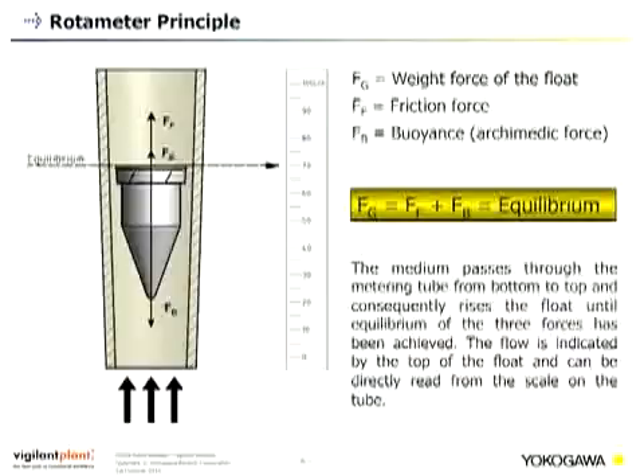The rotameter principle is one of the oldest and most mature principles in flow meters. You have two parts: a conical tube and a float. Three forces act on the float: the weight force, the friction force, and the buoyancy — the so-called Archimedean force. These three forces must be in equilibrium for stable flow measurement. The medium passes through the conical tube from bottom to top, rising the float until equilibrium is achieved. The flow is indicated by the top of the float and can be directly read from the scale on the tube. This is why rotameters must always be installed vertically with flow direction from bottom to top.